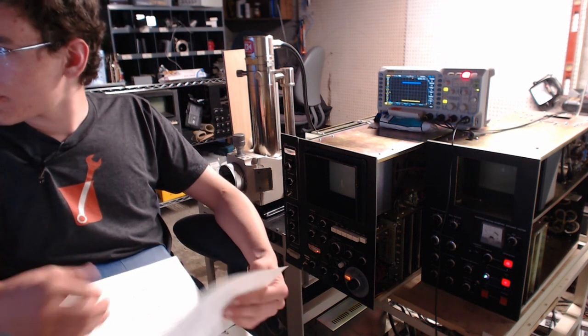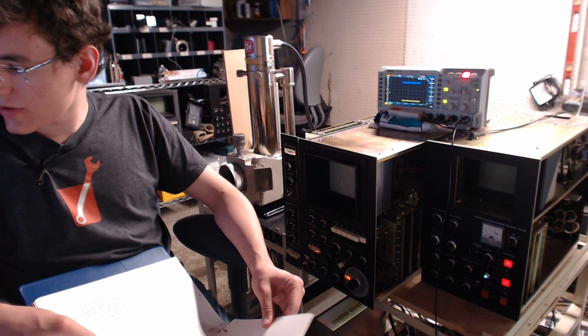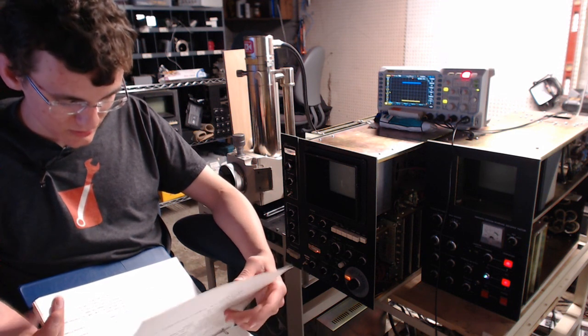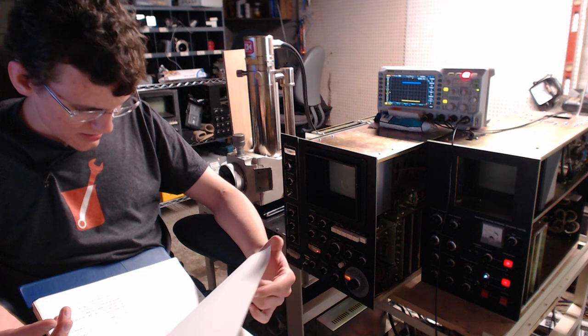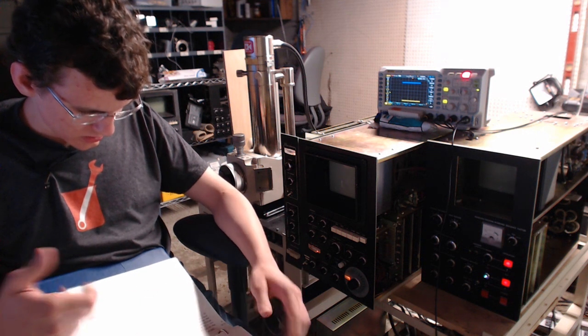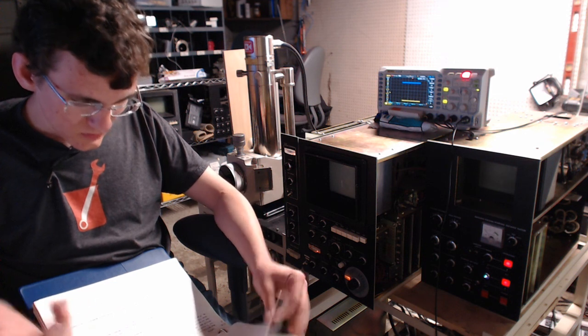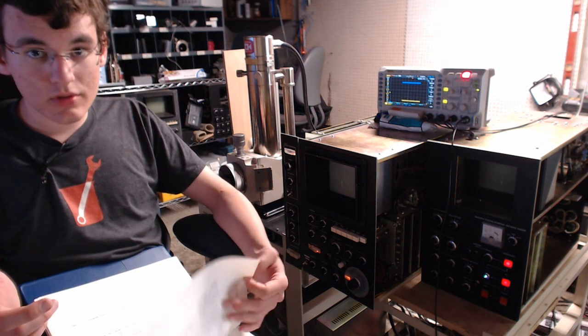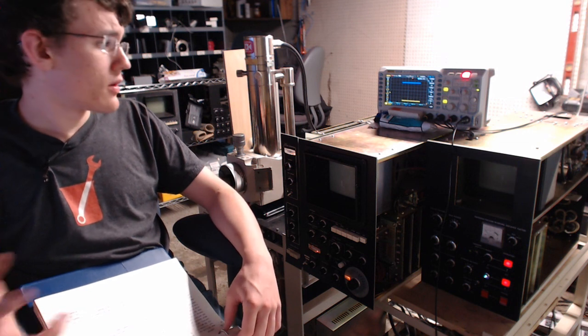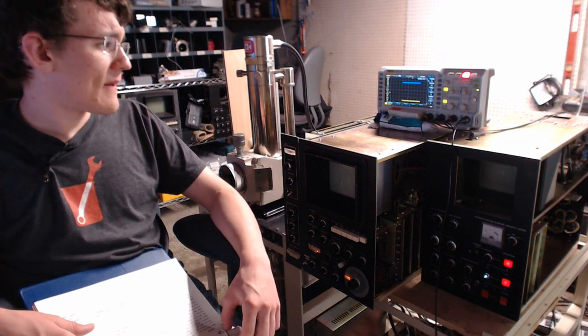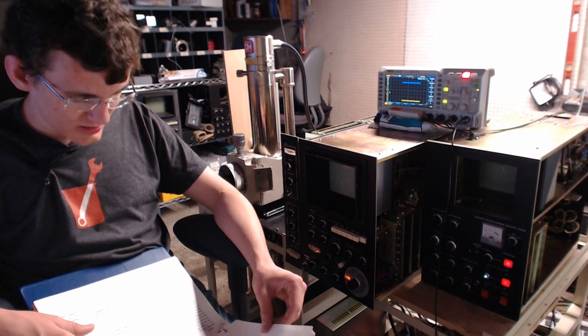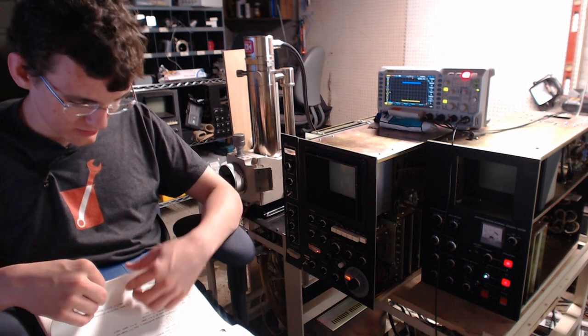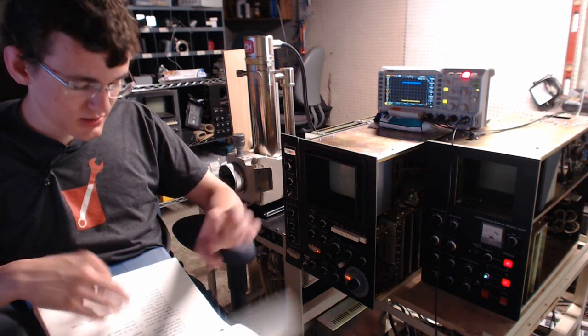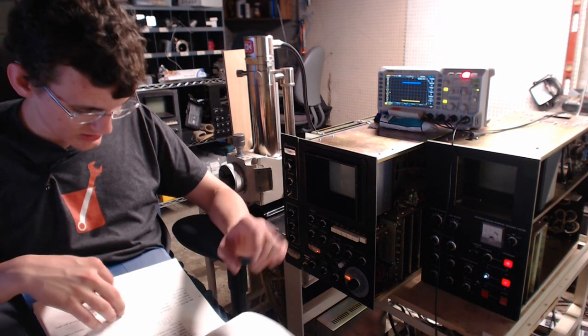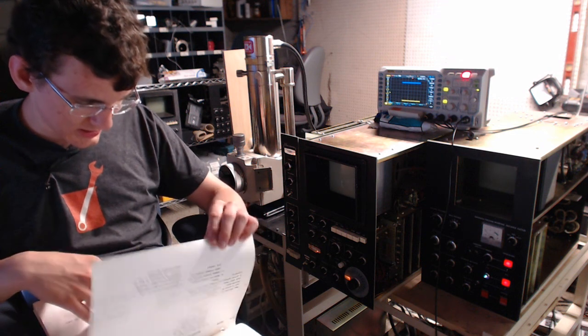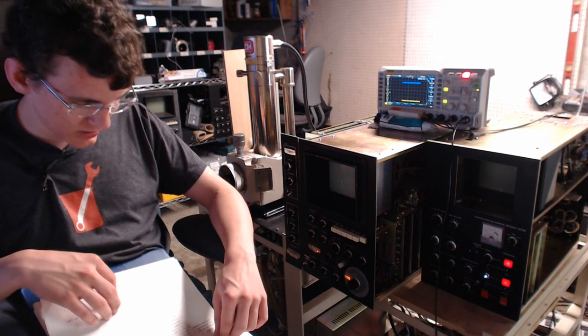Yeah, I don't know what the scintillator bias voltage is. That's what I'm checking on right now, to see if there's a 1 megahertz signal in there somewhere, which would be really telling. You see, changing contrast control is what makes the noise apparent. And so I'm interested in what contrast actually does, because I know it's not a signal processing thing. I know it's a physical thing somewhere inside the scope. As in, it changes the voltage on part of the detection apparatus.